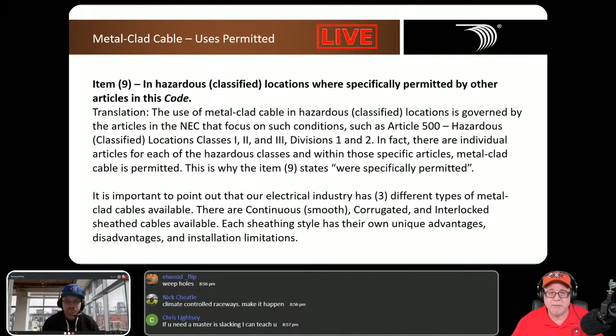So again, you have smooth, which is continuous, corrugated, and interlocked. Interlocked is very limited in its use in a hazardous location. Okay, very limited. But the point of this rule is saying, hey, if somewhere else in the NEC says that you can use MC cable, go for it. And it'll tell you what kind you have to use. Trust me, it'll tell you whether it can be smooth or corrugated or whether interlock's permitted. It'll tell you right in those other areas of the code. Okay, so that's the reason why it says permitted by other articles of this code, because somewhere else in the code might permit you to use it. And that's giving you an allowance to do that.